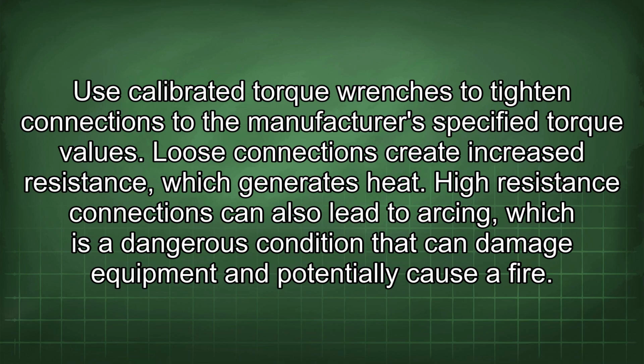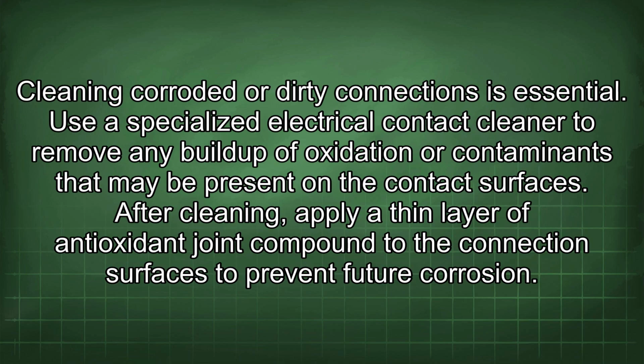Higher resistance connections can also lead to arcing, which is a dangerous condition that can damage equipment and potentially cause a fire. Cleaning corroded or dirty connections is essential. Use a specialized electrical contact cleaner to remove any buildup of oxidation or contaminants that may be present on the contact surfaces. After cleaning, apply a thin layer of antioxidant joint compound to the connection surfaces to prevent future corrosion.